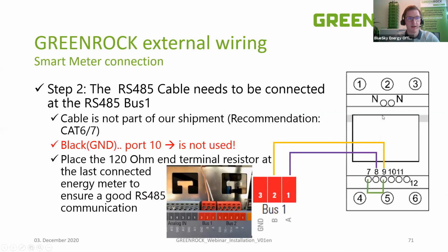This is how the schematic of the energy meter looks like. You here have the connection ports 8 and 9, and these ports need to be connected via a network cable, for example, so just 2 wires, to the GreenRock EMS. On the EMS, you have a connection called bus 1. This is the RS485 connection point. Just place pin A of bus 1 to pin 8 and pin B of bus 1 to pin 9 on the energy meter.